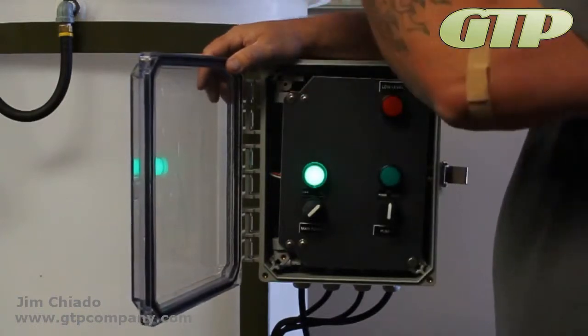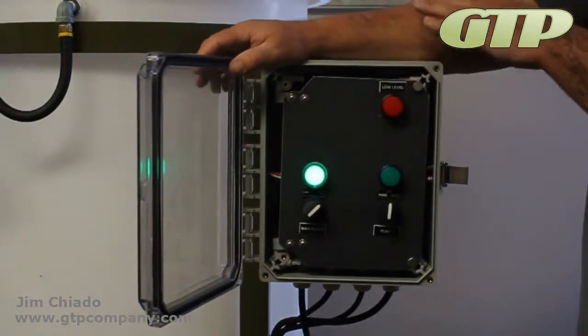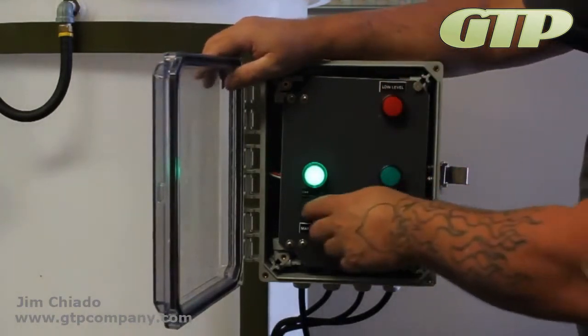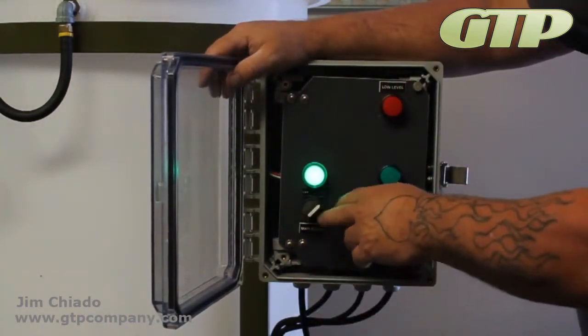It may not be in low level but if it's broken in there, it will fail low level — that way we don't accidentally drain the tank or we don't accidentally run dry on our pump.